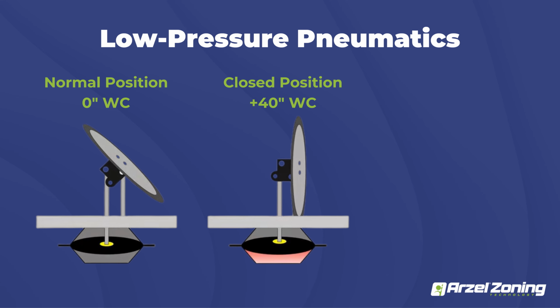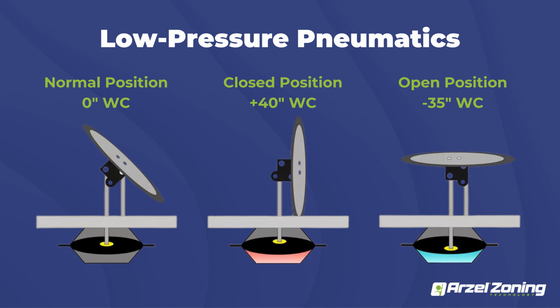Then when we go to close the damper, we send pressure and it pushes against the diaphragm in the bottom of the damper there, just like the picture. That's going to push on that rod and close that damper off. When we go to open, same kind of concept. It's going to pull a vacuum on that diaphragm, and that's going to actually open up that damper. If you guys have seen the inside of a pressure switch, the rubber diaphragm is very similar to what's on the inside of our dampers themselves, just a lot thicker rubber material, for better longevity.